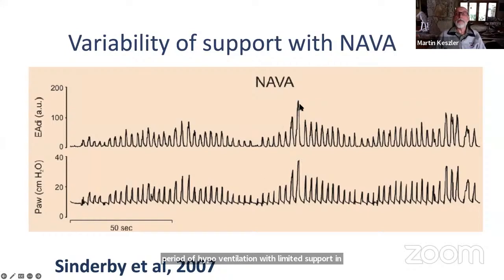And here maybe somebody banged the incubator or spoke too loudly or God forbid touched the baby, and there's a burst of very strong inspiratory effort resulting in peak pressure of almost 40 centimeters. So this is probably not something that I would want to apply to my patient. With non-invasive NAVA being an open system, you probably never transmit really high pressures. But with intubated patient, this could potentially be dangerous.